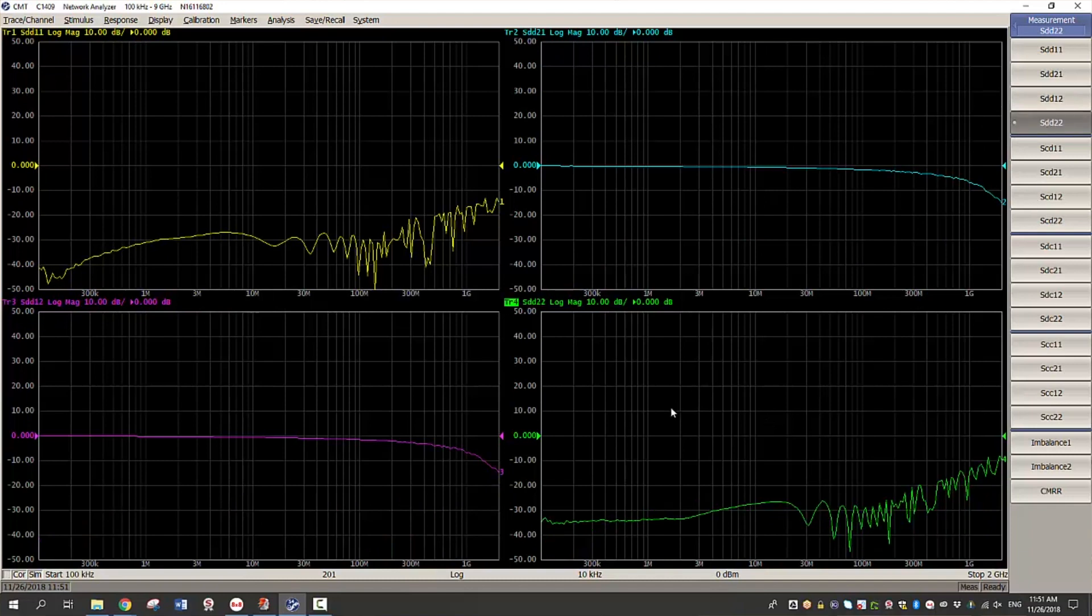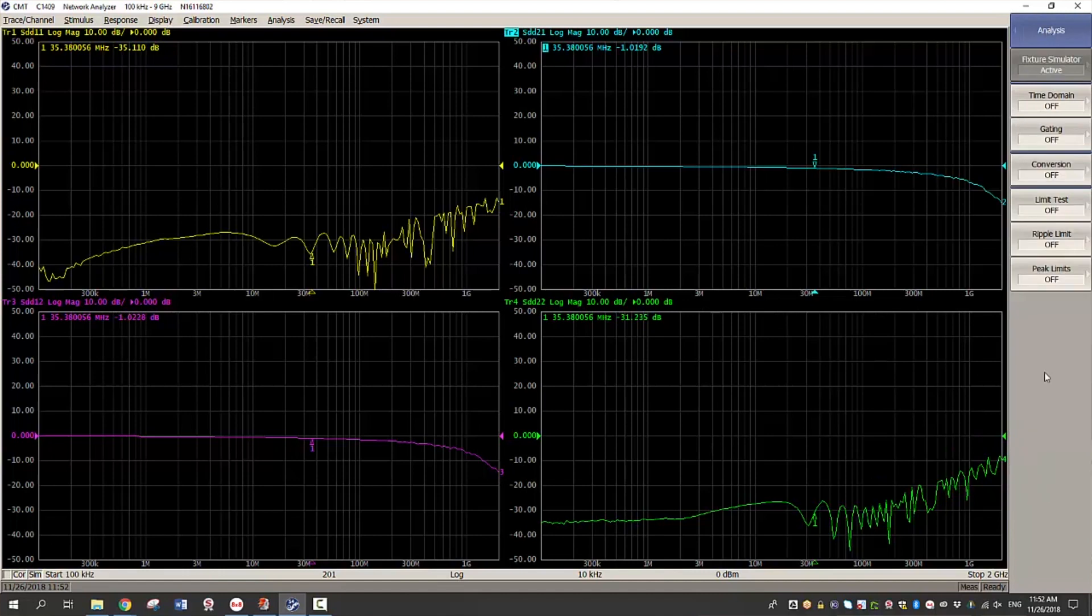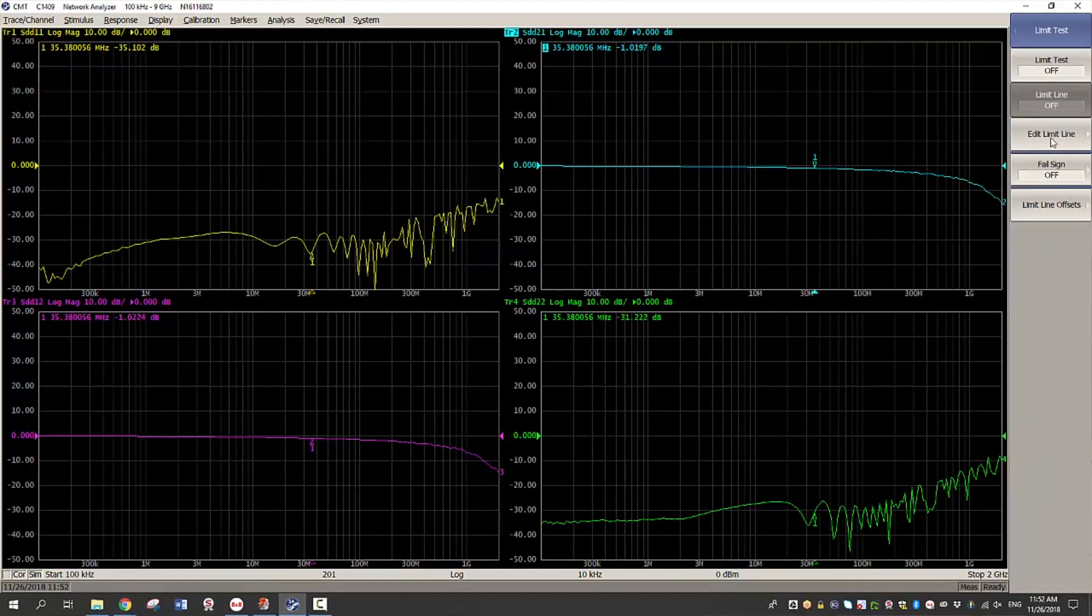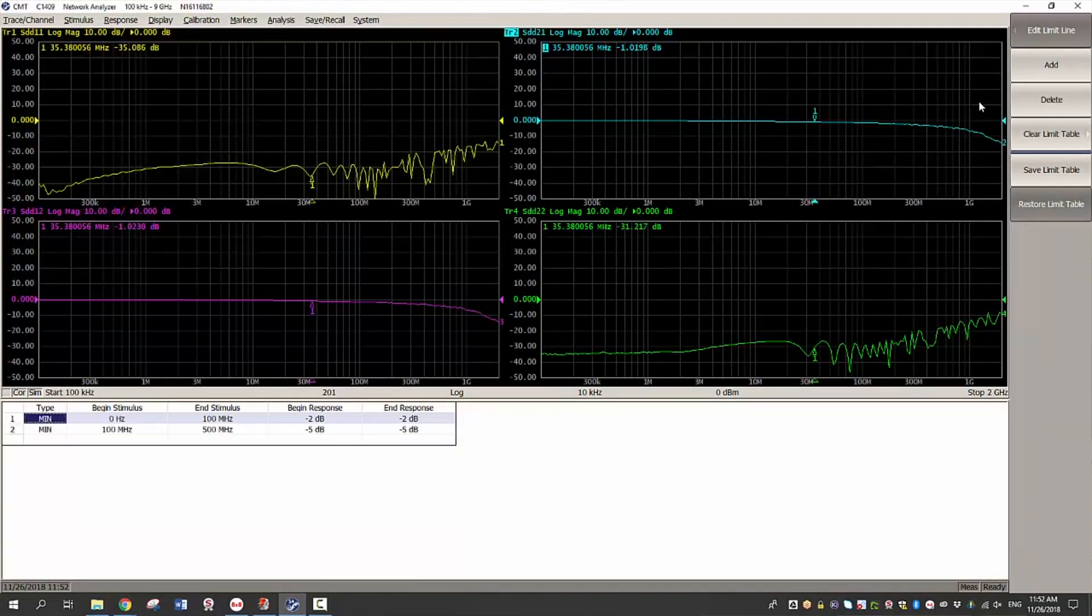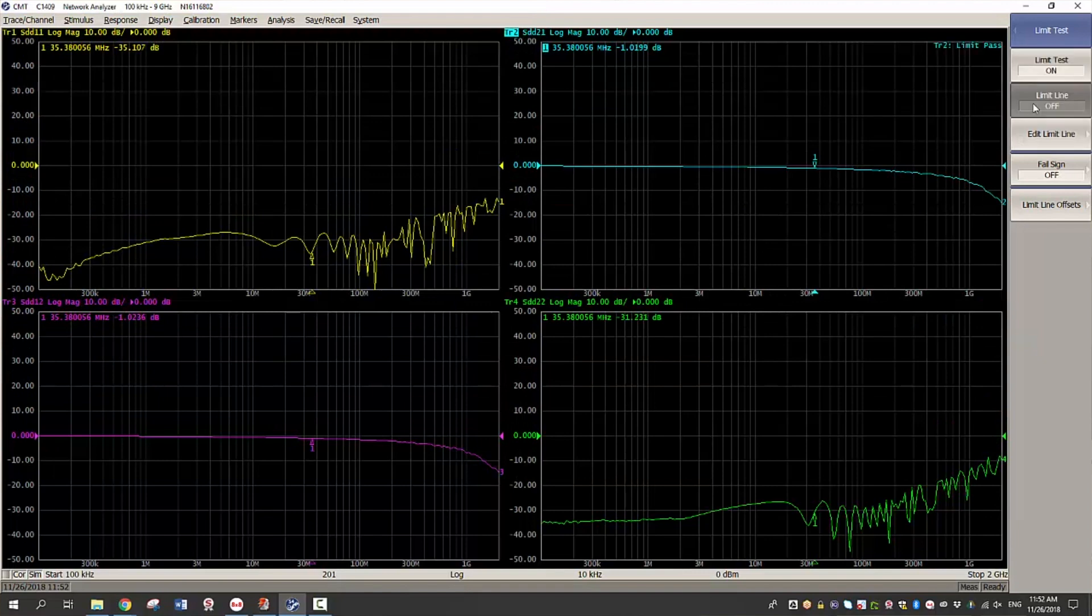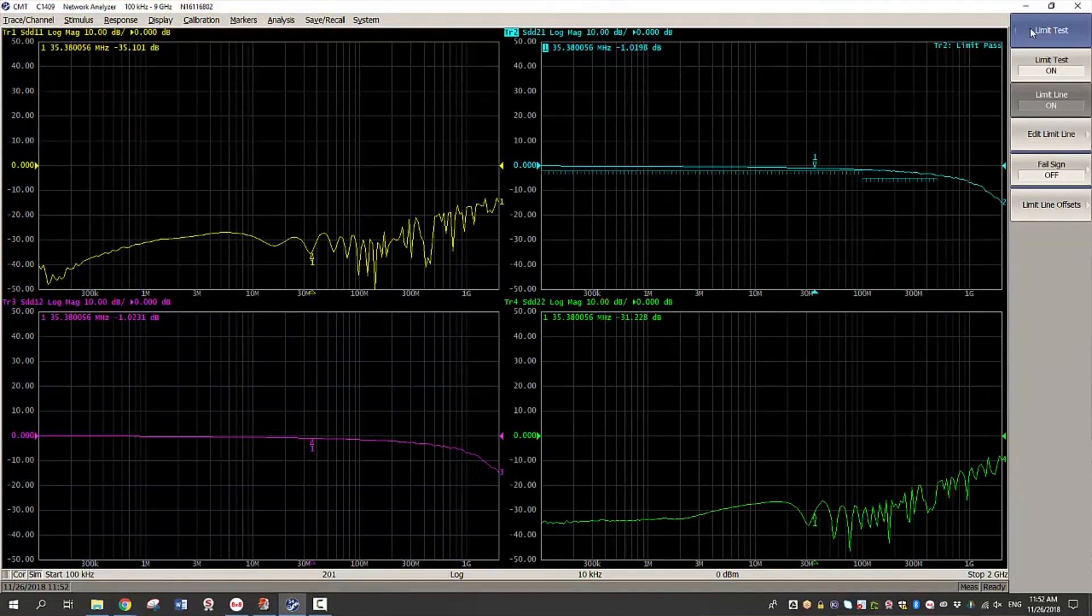And now we see the differential measurements in frequency domain. Adding markers helps view the measurements in detail. Also what you can do is you can add limit line to see whether the measurements passes or fails. So as you can see this cable on the test passed.